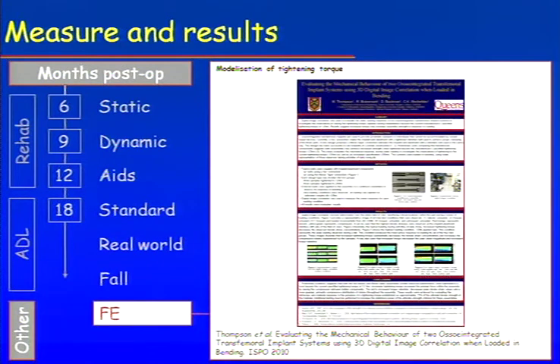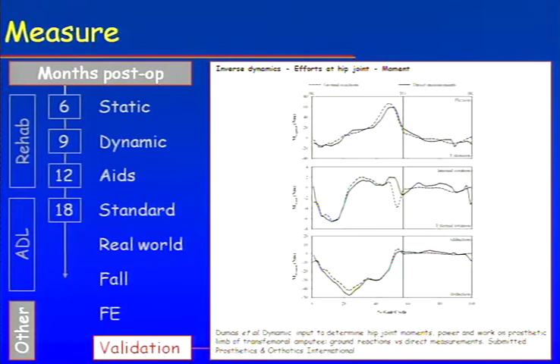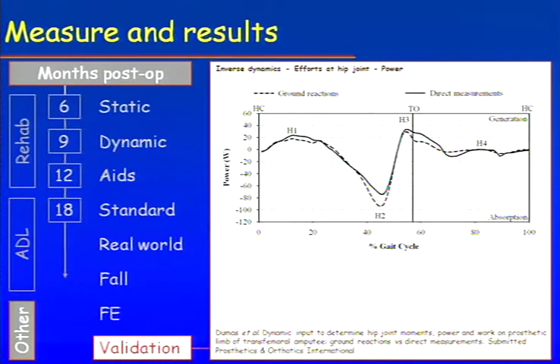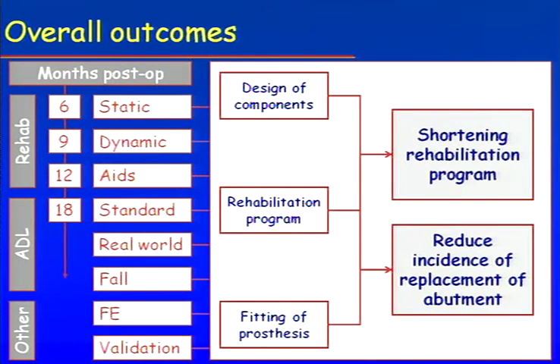Another analysis we can do is look at the correlation between the load and the tightening torque of the abutment. Another interesting factor is inverse dynamics. Typically when you want to measure load, you use a set of equations called inverse dynamics — using video data and force plate data to calculate forces applied at the ankle, knee, and hip. The inverse dynamics calculate the load while the transducer measures the load, so we can compare the two and validate gait lab measurements at the hip joint level. Altogether, what we are trying to do is improve the design of prosthetic components, improve the rehabilitation program and prosthesis fitting — and hopefully those combined will shorten the rehabilitation program and reduce the incidence of abutment replacement.